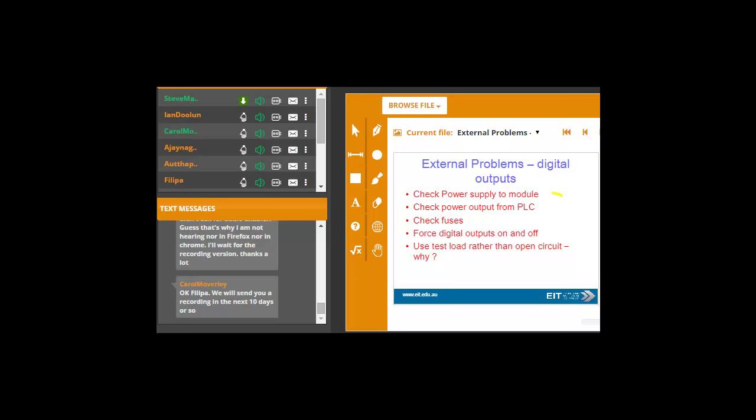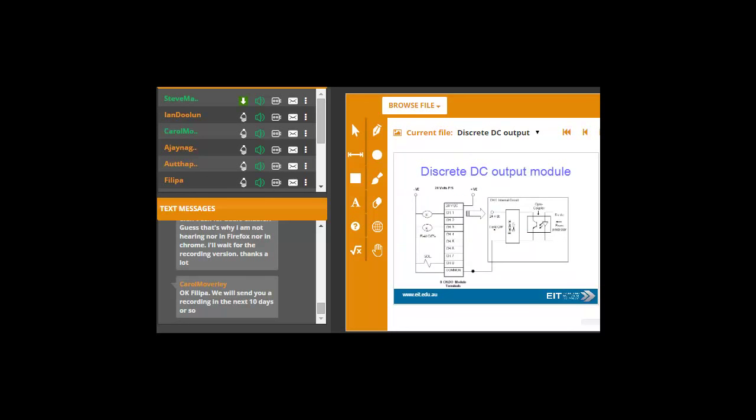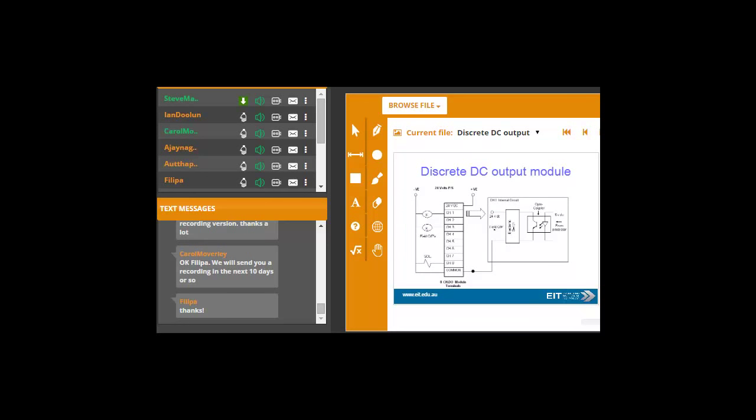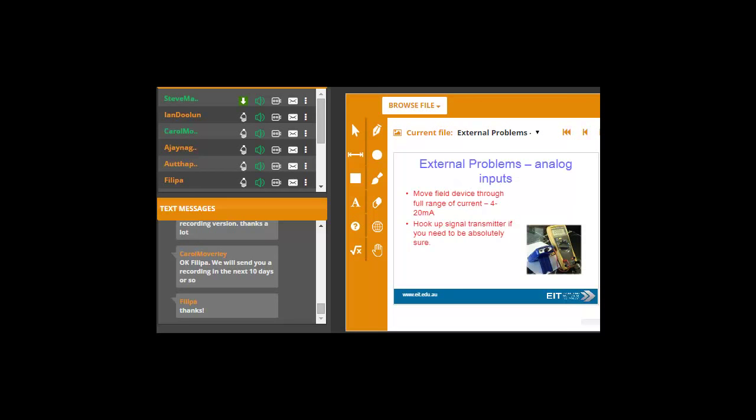Digital outputs, obviously, check the power supply to the module, and obviously, with digital inputs and outputs, you have the thing called sink and source. If it's a digital input and it's a sink module, then the current flows into the input. So you supply the plus 24-volt DC flows into your card. That's called a sink input. You could also have source inputs as well, but I'm not going to talk about those. So here, again, check the fuses. Check the digital outputs are on and off. Best to force them on and off and see what's going on. And again, always test the load. Test your outputs with load rather than open circuit. Why? Because they may not deliver the current that you require, and that's where the problem occurs. So make sure you test them under load.